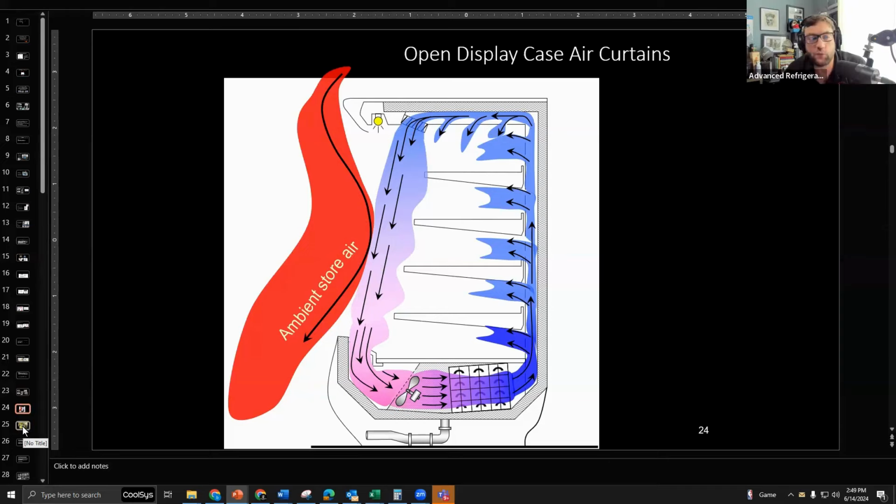There's a manufacturer of case that everyone dreaded. It was a three different chambered air coil unit. You had this primary coil, which was at -10. It was an open case. Then you had a secondary air that didn't go through the coil, but it was underneath this. And then you had an ambient set of fans that would blow another third air curtain across it. So if one of those three fans messed up or went wrong, it was just humidity central.